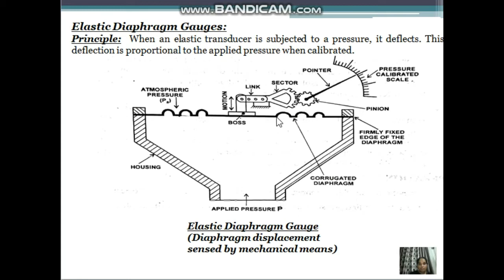That is, the diaphragm tends to move upwards due to the applied pressure. This deformation of the diaphragm is proportional to the applied pressure. This deformation is magnified by the link sector pinion arrangement. That is, the linear displacement of the diaphragm is converted to a magnified rotary motion of the pinion. When the pinion rotates, it makes the attached pointer assume a new position on the pressure calibrated scale, which becomes a measure of the applied pressure. As the top side of the diaphragm is usually subjected to atmospheric pressure, elastic diaphragm gauges usually read gauge pressure. So this is the working of elastic diaphragm gauges.